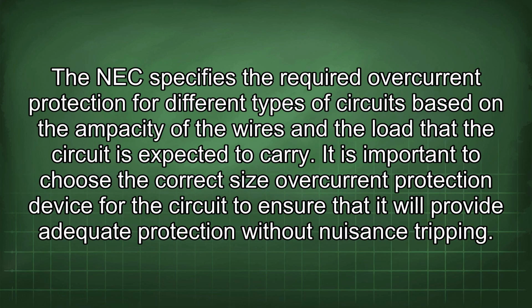The NEC specifies the required overcurrent protection for different types of circuits based on the ampacity of the wires and the load that the circuit is expected to carry. It is important to choose the correct size of overcurrent protection device for the circuit to ensure that it will provide adequate protection without nuisance tripping.